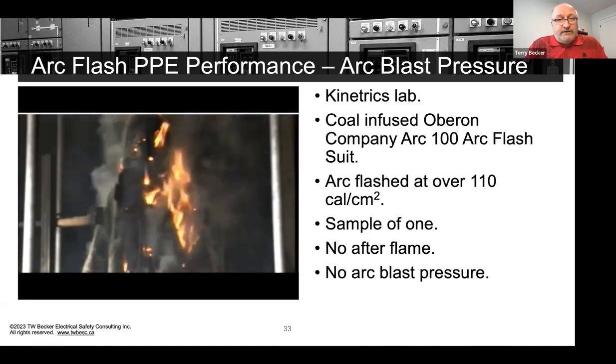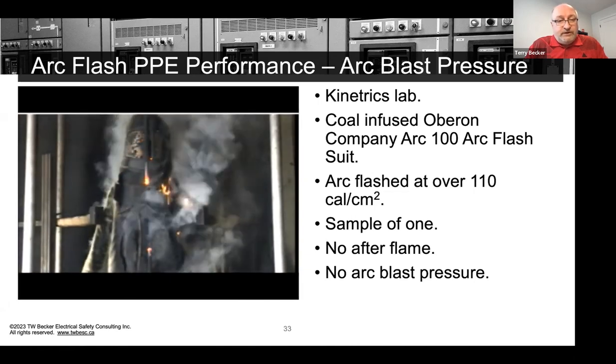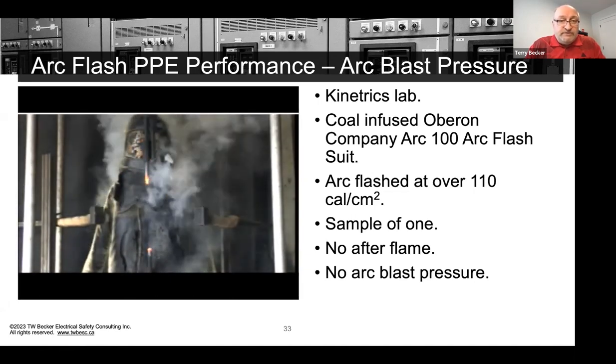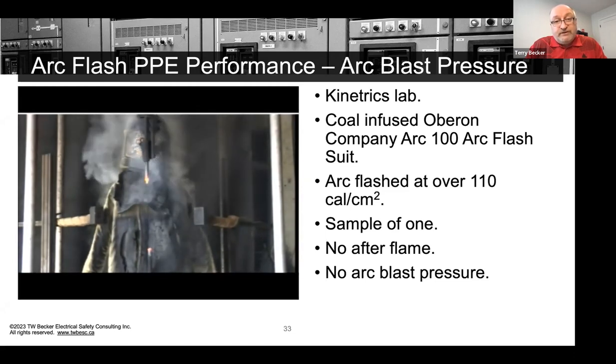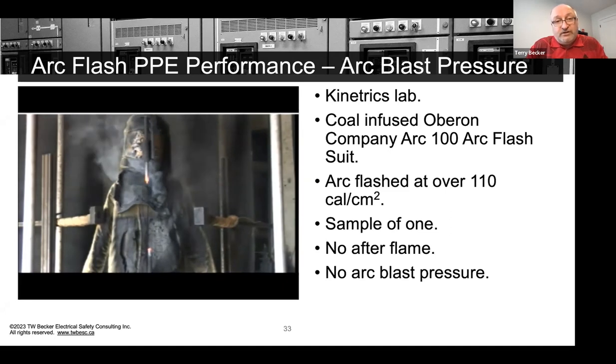So 1001, 1002, 1003, 1004, 1005. So that's acceptable where it's self-extinguished. So flame-resistant fabric that's arc-rated will self-extinguish if it does ignite like that. So we think it flashed off the coal dust. Now, that's not a normal arc flash.